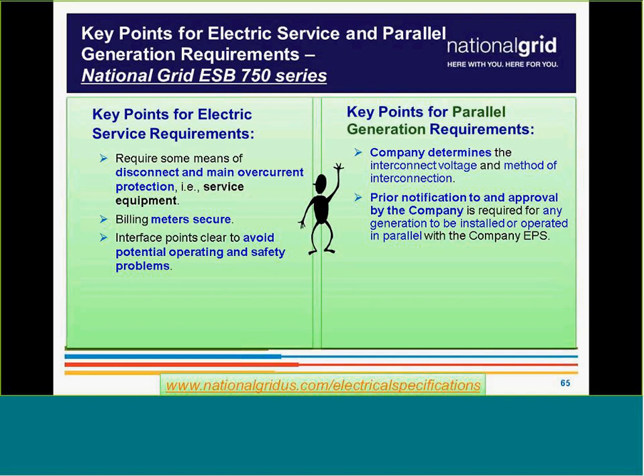When you're looking at parallel generation, there are other things to keep in mind. It's up to the utility to determine the voltage and the interconnection point. You may propose something, but we do reserve the right to say we can't fit you on this feeder. We need to install an express feeder, or upgrade a transformer size, or change what type of service you have, depending on the size of the generation. So keep that in mind as you're applying.